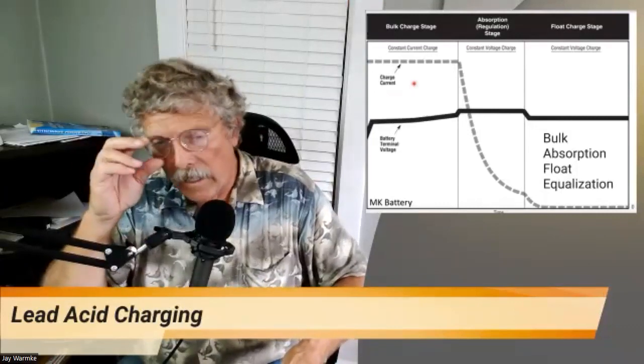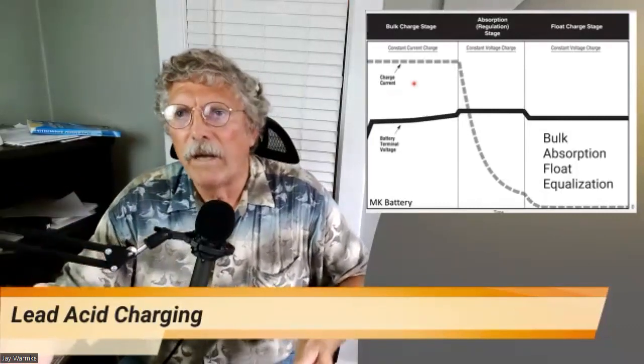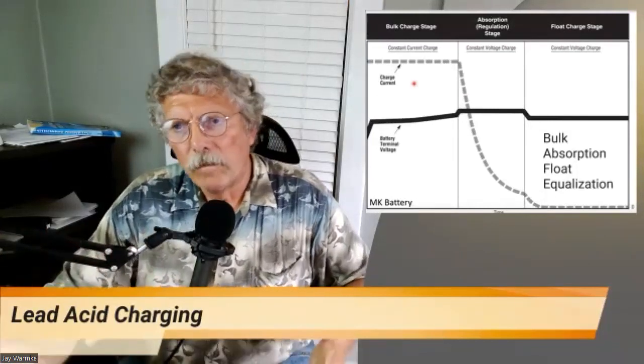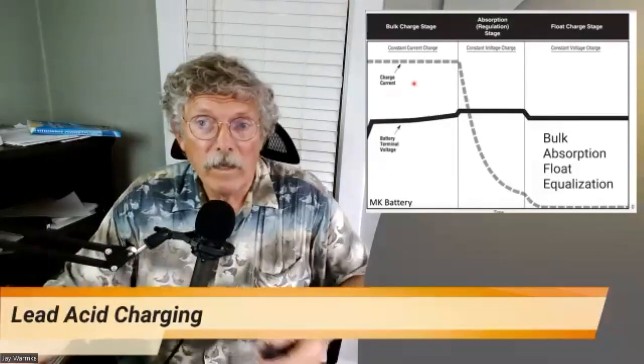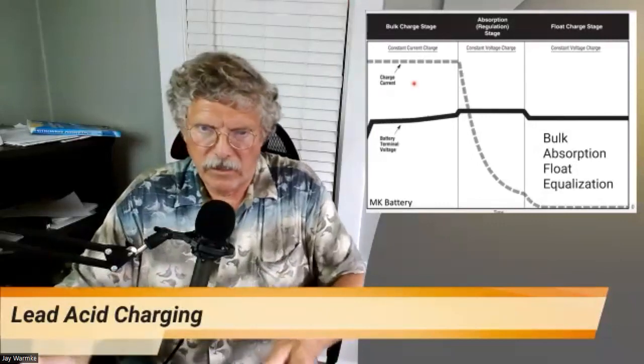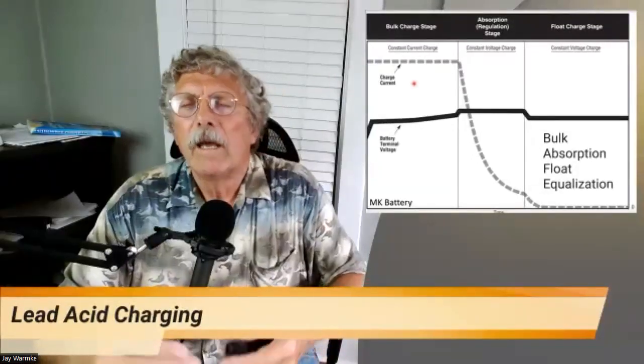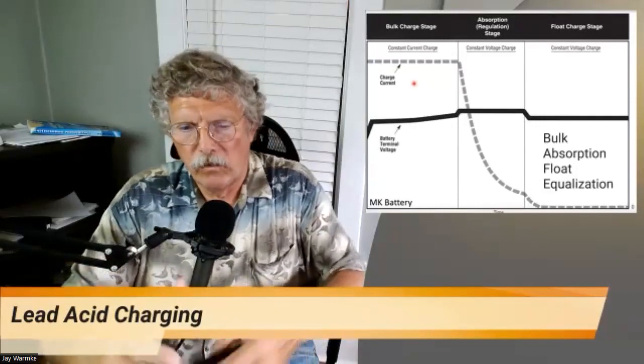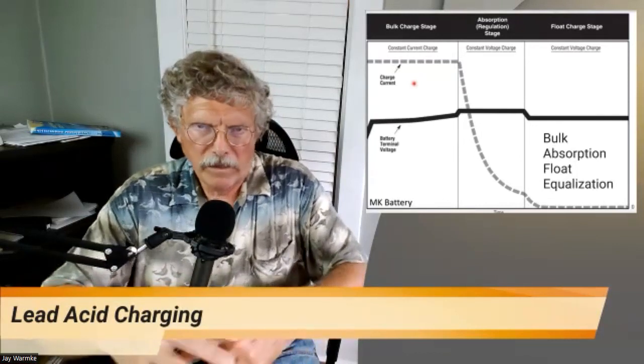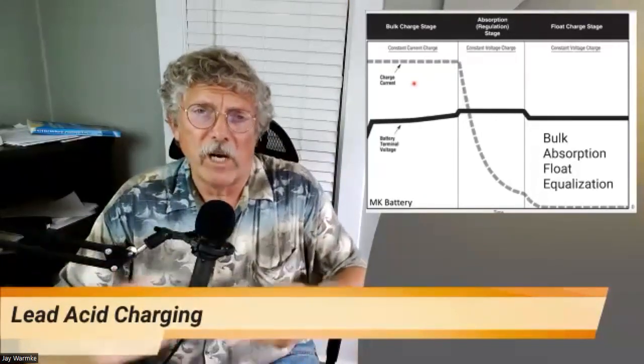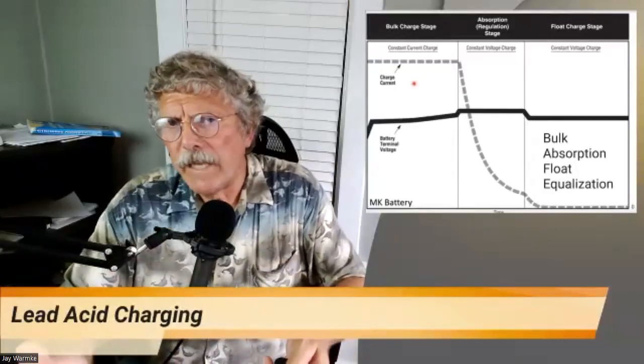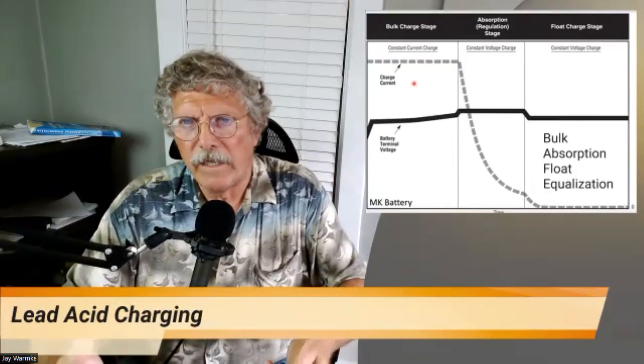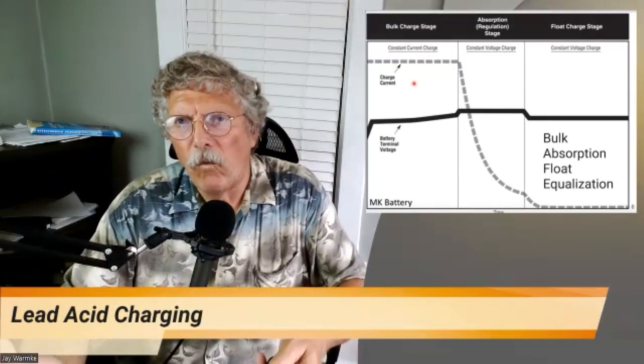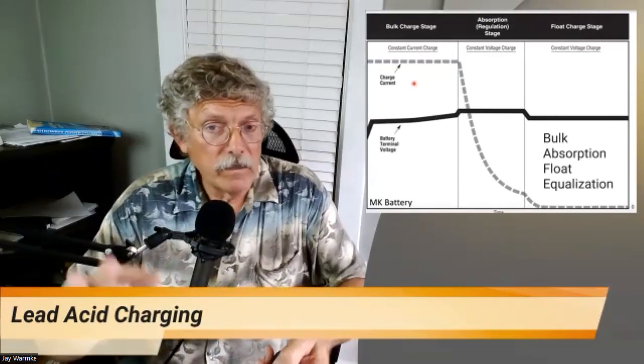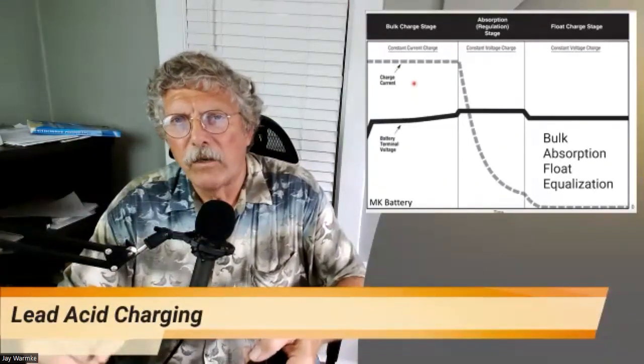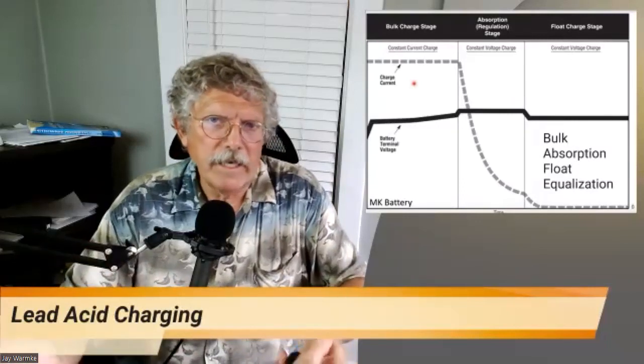With lead acid, those of you who've gone through my classes know we talk about bulk charging, absorption, float, and then once a month there's an equalization, because lead acid is basically sulfuric acid. Sulfur builds up in the battery, so you end up having to, I always think of it like a self-cleaning oven, where it goes into extreme overcharging, boils the electrolyte, and cleans out some of that solidified sulfur, the sulfation within the battery, giving it a good cleaning. That happens about once a month with lead acid batteries. So if you have one of those systems, you may hear the battery bubbling in the back of your garage, thinking something's wrong, but it's just cleaning itself.